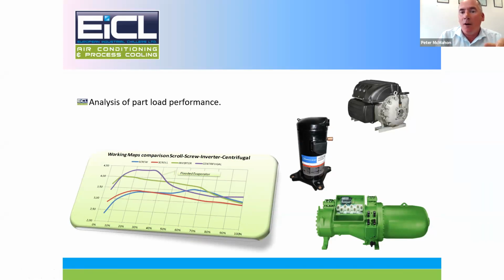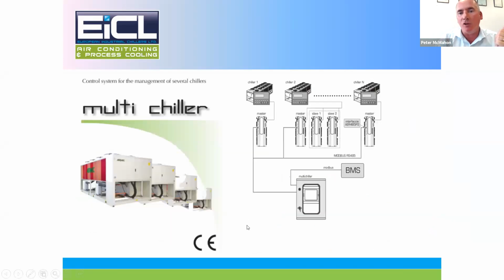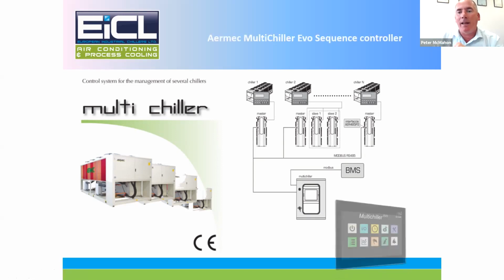So where you often will have a system where you might have two chillers, and if the load increases, you'll run one till that can't cope anymore, then you might bring on the other. We can be much more intelligent how we manage that. So Aermec developed a component called the multi-chiller sequence controller. And what it does is it communicates with each chiller that you have, two or more on the system. And when the first chiller is becoming inefficient, let's say at 70%, it will now bring on the second chiller. The two of them will run at lower load, but at a much greater efficiency. Okay. So that is the second component.